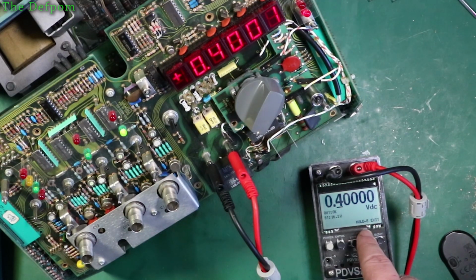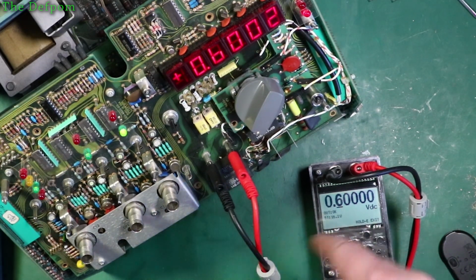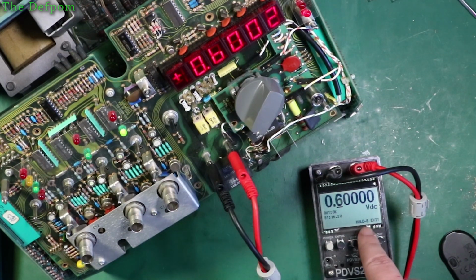Now you can see it's creeping up a little bit there. Right, 400, starting to creep up. Again, it's not this, it's the multimeter which is doing that. See, it's 2 millivolts over now. Oh sorry, 200 microvolts over. 300 microvolts over. 300 over still. There you go, starting to go to 400 over. Then as you get close to the set point, it comes back down again.